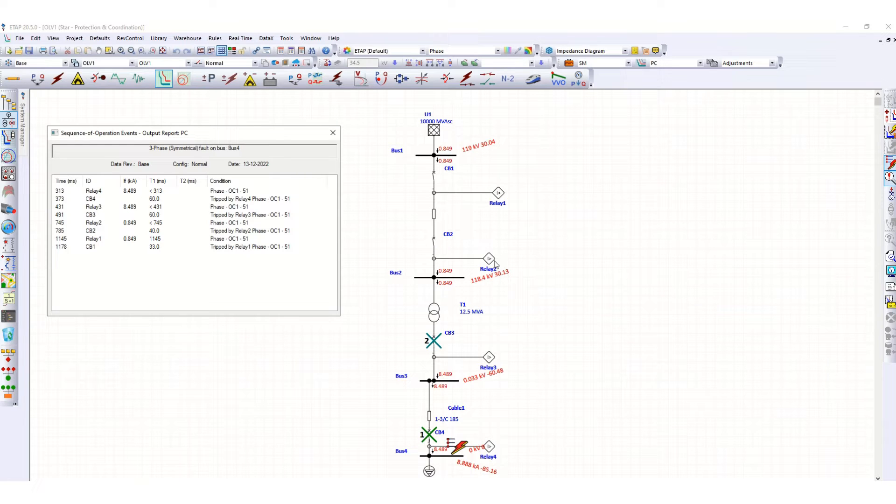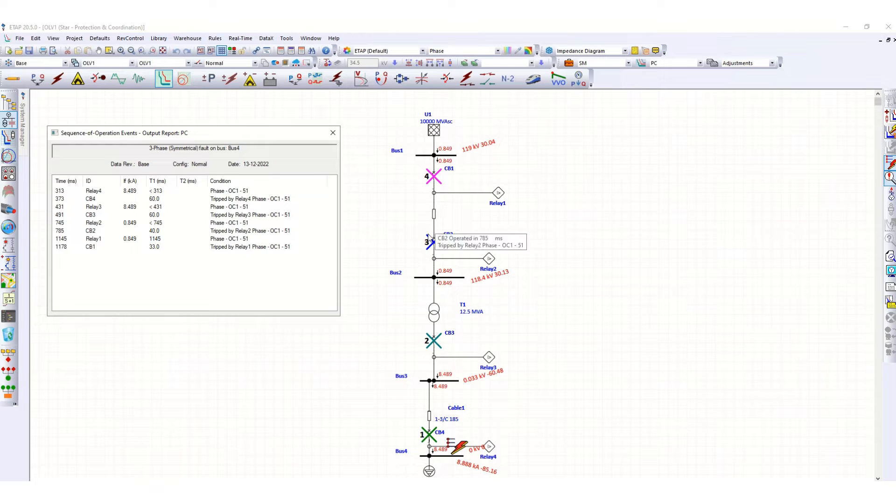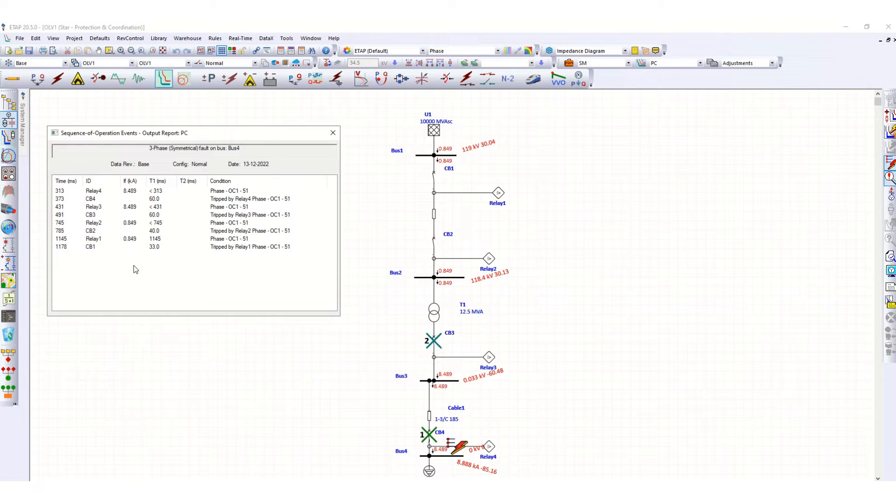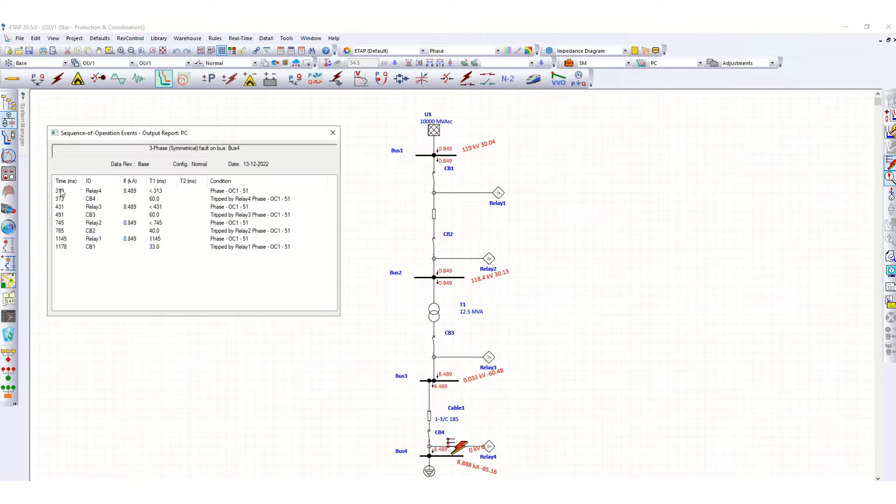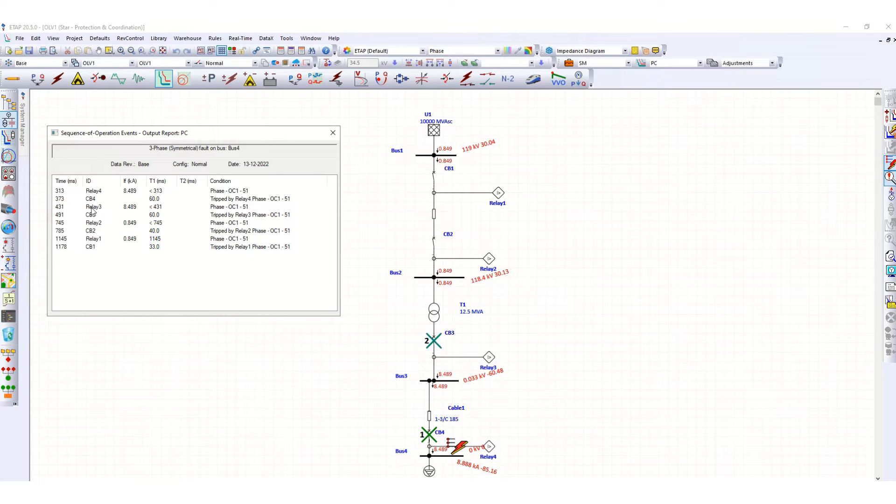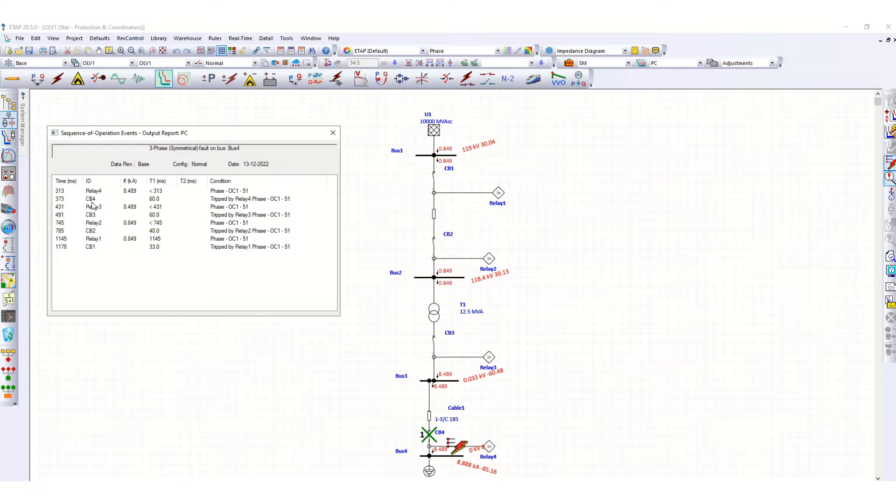Next, relay 2, this relay number 2 is tripping circuit breaker CB2, and finally relay 1 is tripping CB1. These are the times when a relay is operating, picking up, and corresponding circuit breaker is being tripped by the corresponding relays.